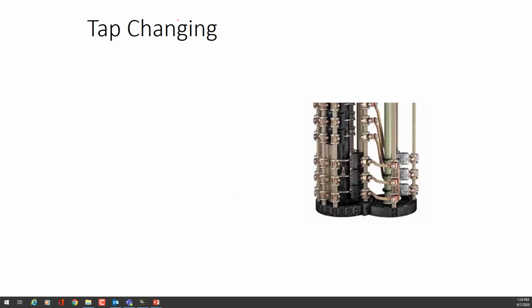Now, tap changing. This can be quite a hazardous situation. Taps can be changed on a transformer in several ways. One is the manual reconnection of them. So you physically go there, you undo the terminal, and you put your wire on a different terminal. So manually reconnecting and re-terminating it. Obviously, the hazards with this, we have to ensure that the primary is completely disconnected before we go changing taps. So you have to be wary of this.